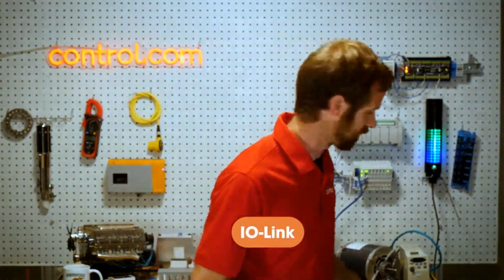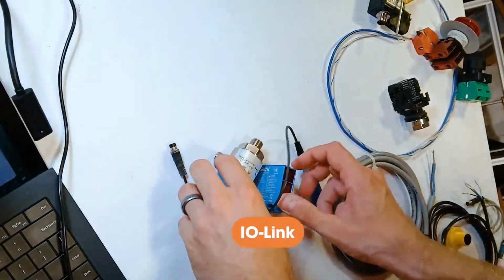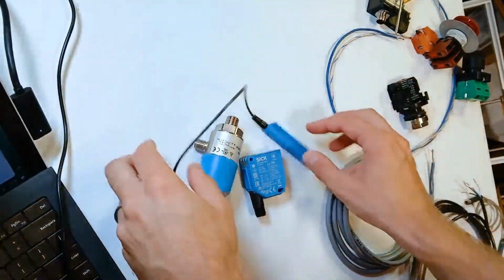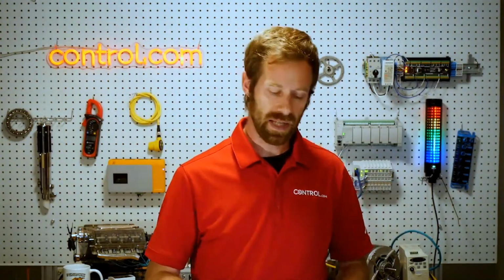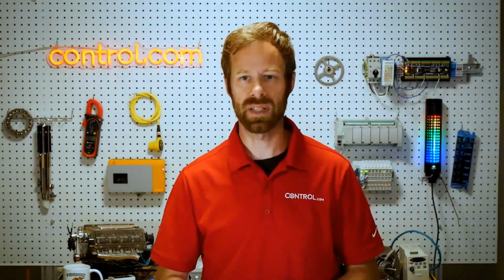I've got a couple of IO-Link devices here. And one of the benefits of IO-Link, like I said, is the ability to send data two different directions. So it can handle a few different things. First of all, we can still set set points. We can determine those set points, and we can receive a digital signal, which is input information based on the process, just like those discrete sensors. We can send it a command and say, I want you to tell me if a box is more than 4 inches away, and send a high signal. And it will. Great for a replacement of a discrete sensor.